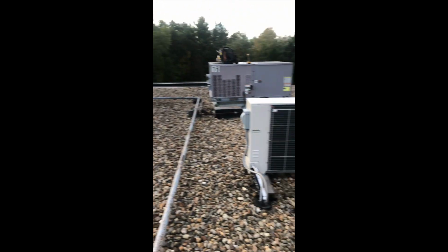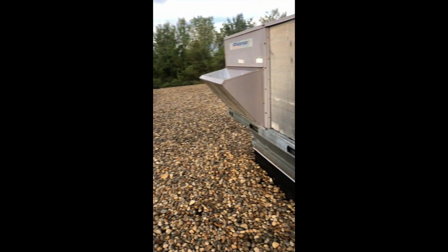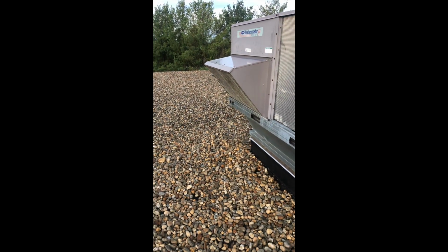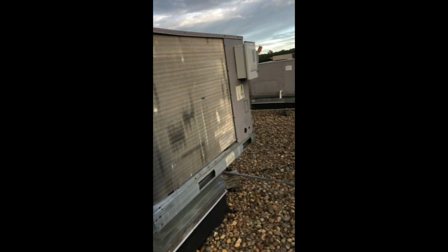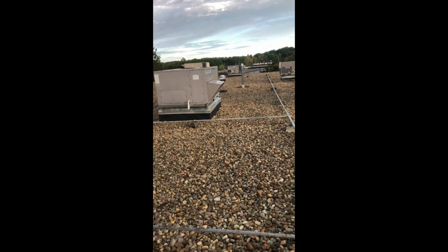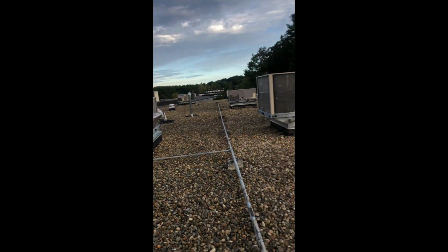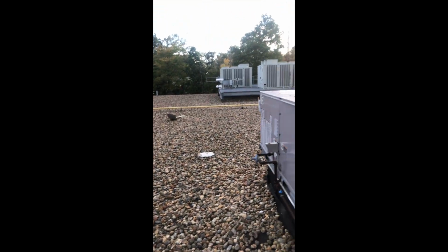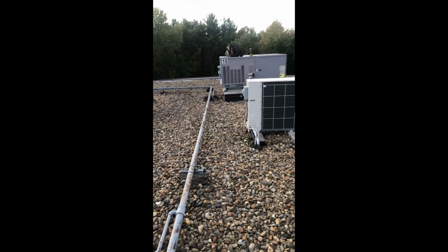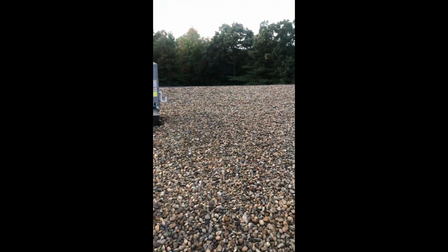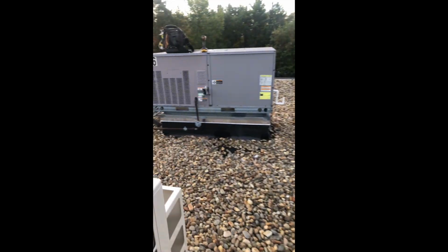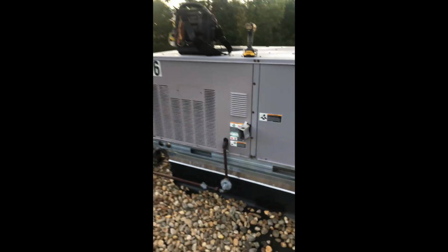So basically what I do is come up and check, because if you get a heat failure call, if your inducer motor is on and indoor fan motor is on and it's not hot, that tells you something. So I come across all these units and find one right here. Inducer motor is running, but it's cold.